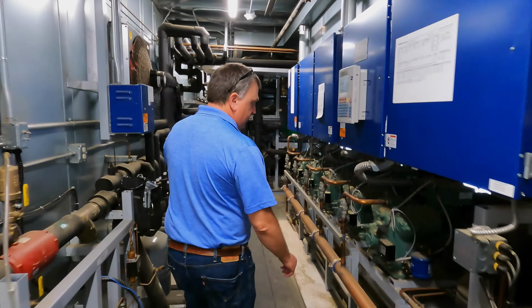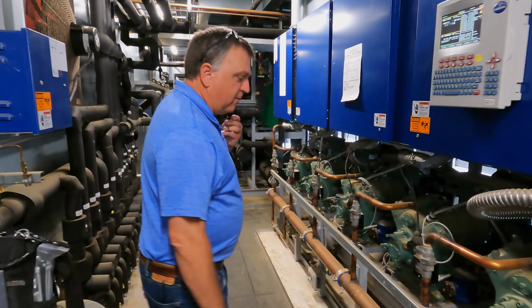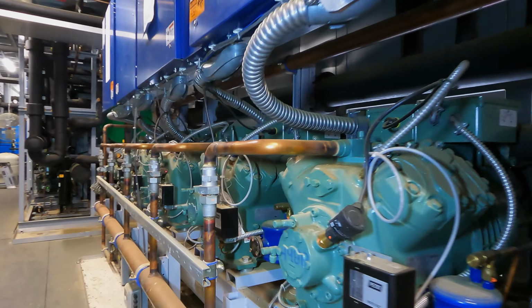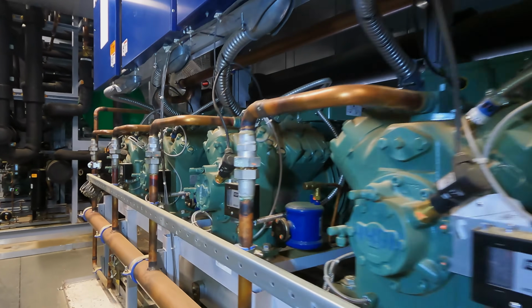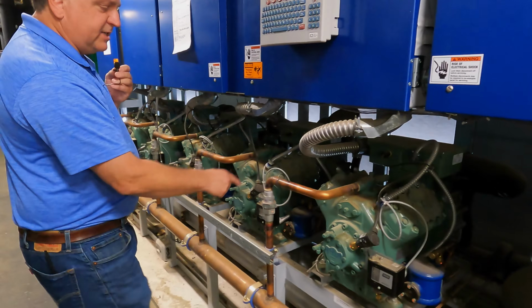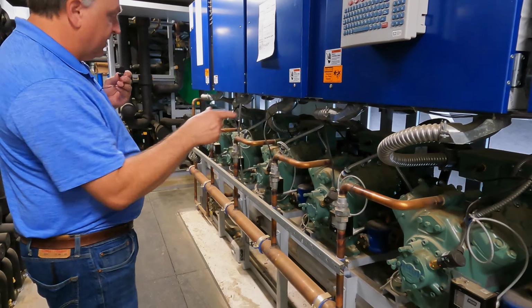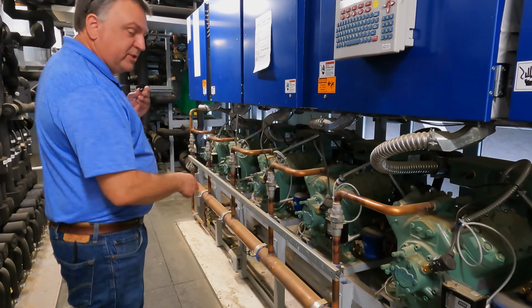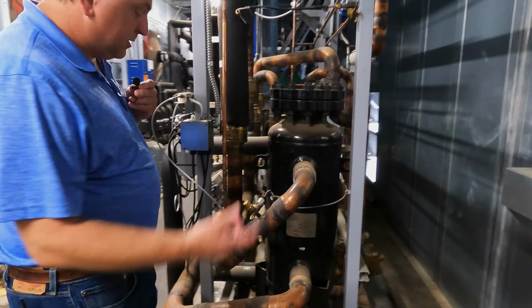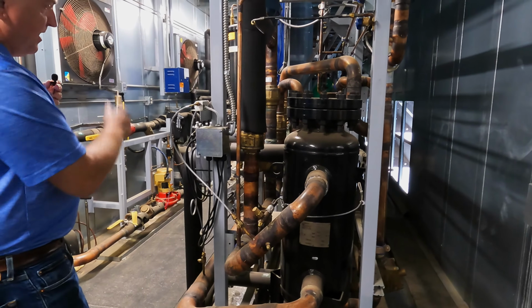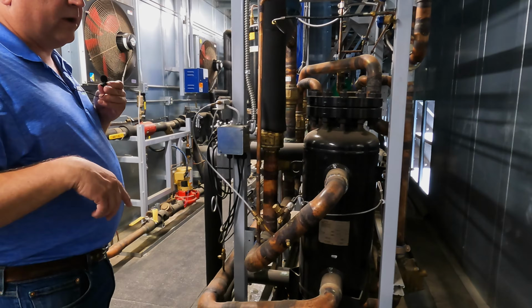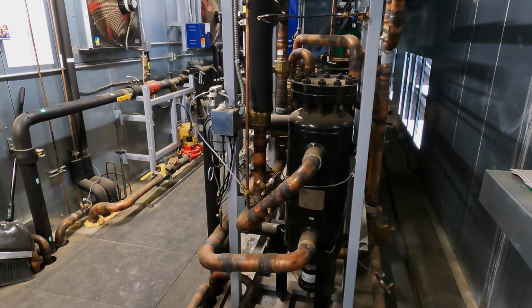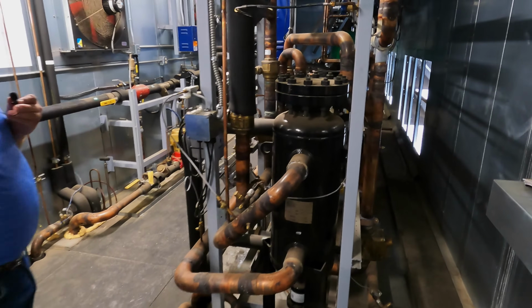Let me walk you through the operation of this 449A parallel rack. Of course, we have our compressors, right? We have 5 compressors. This is our discharge line, a discharge leg. We're leaving the compressor in a high pressure, high temperature state. So as that refrigerant is leaving the compressors, it's taking some oil with it. We want that oil to get back to the compressors, and that's what our oil separator does.